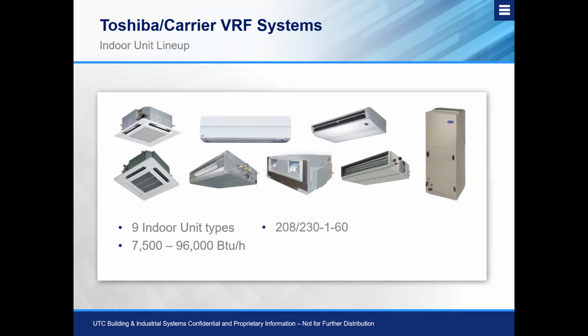These are all available in 208, 230 single phase applications. And again, just like on the Carrier style system, they have integral ventilation and condensate lift mechanisms on most of the models. So the cassette styles have the outside air knockout and the condensate lift. Of course, with any outside air into the fan coils, that air needs to be pre-treated. And just like we had prior to that, the low static, medium static, and high static ducted units on top of the vertical air handling unit can all have outside air mixed in at the return. And of course, that air needs to be pre-treated.